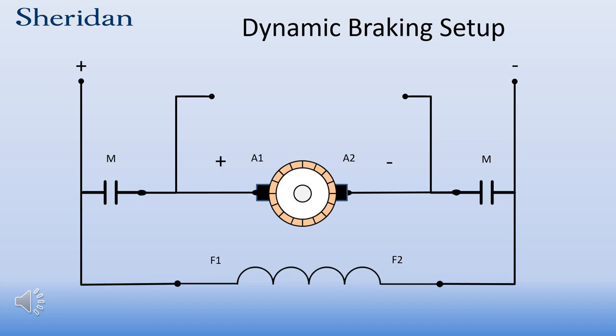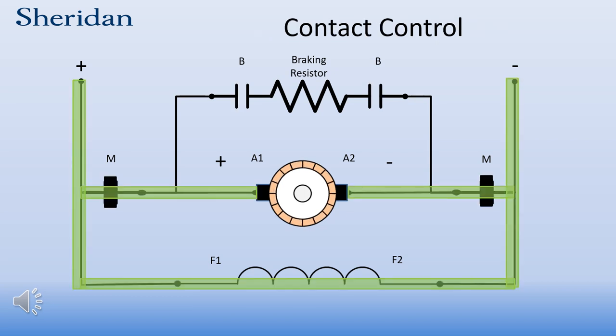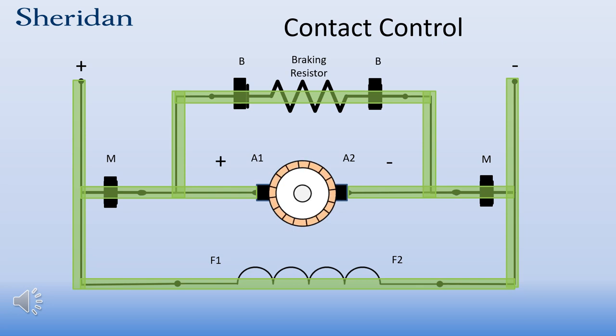Let's look at the dynamic braking setup. A resistor is connected to the armature through a set of load contacts, shown here as B for braking relay. When the contacts close, the resistor will be across the armature. It is very important to note that the B contacts and the M contacts must be controlled so they cannot be closed at the same time. If they are, the braking resistor would receive supply voltage and current would continuously flow through it, causing it to heat up and possibly burn up.